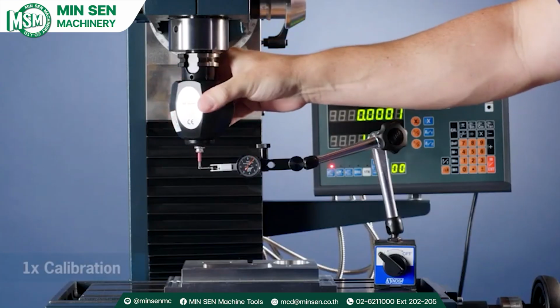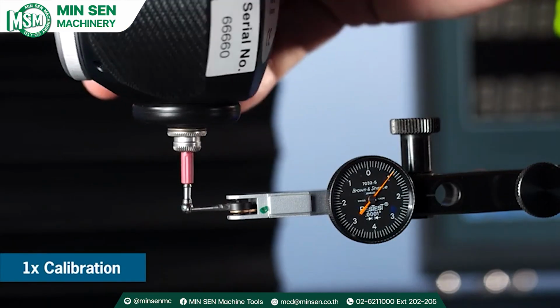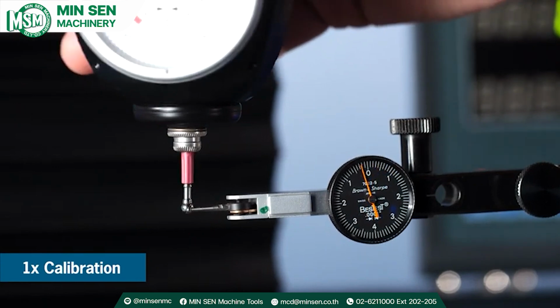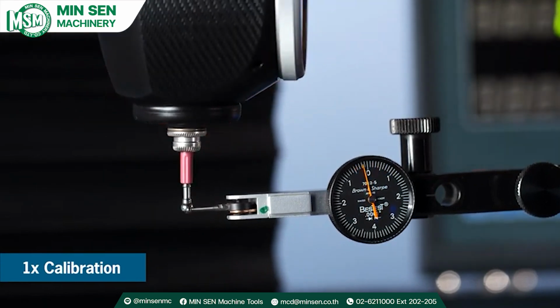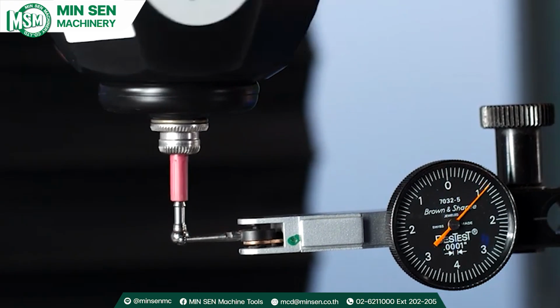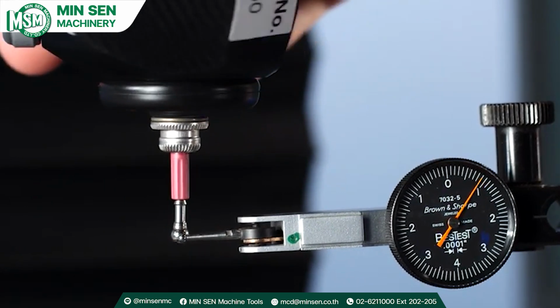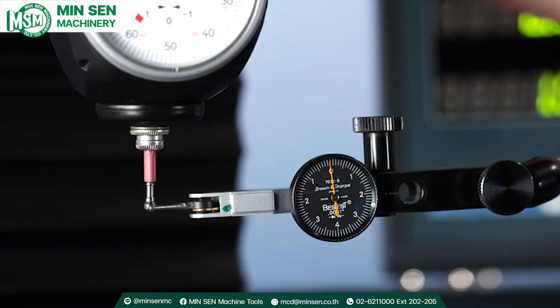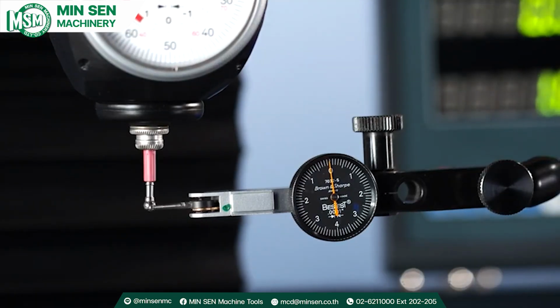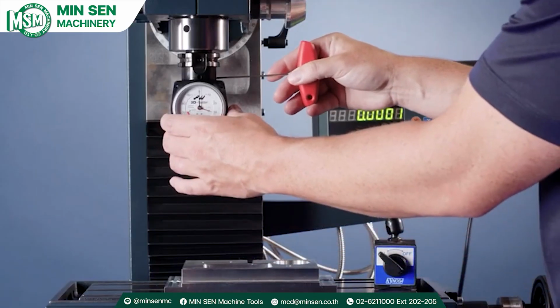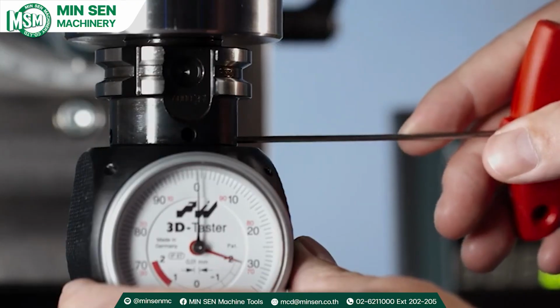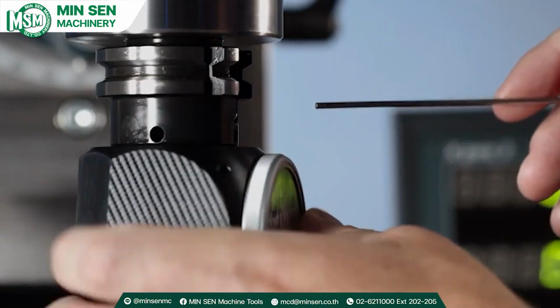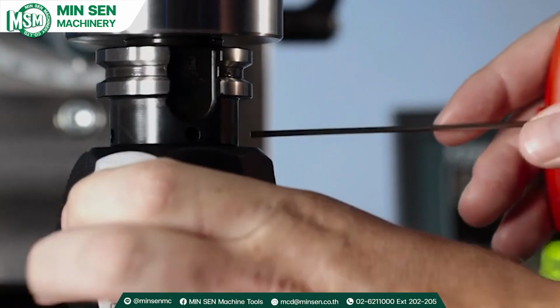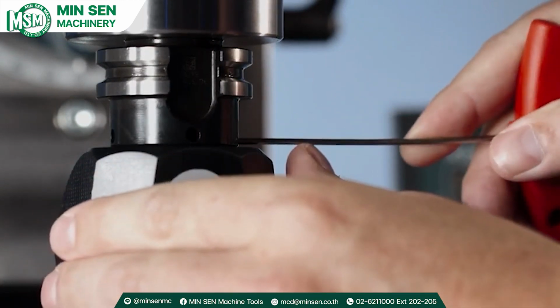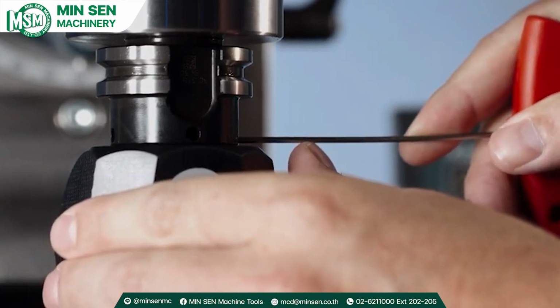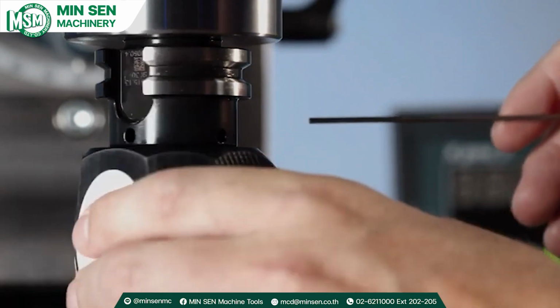To adjust concentricity relative to the spindle, begin by placing a standard indicator perpendicular to the sensor tip. Rotate the sensor to determine the degree of runout present. Once you've identified the position of runout, use the set screws located at the top of the sensors to make any adjustments. As a tip, when loosening one side, remember to tighten the set screw on the opposite side. Once you have the desired runout accuracy, you're ready to begin using the HAIMER 3D sensor.